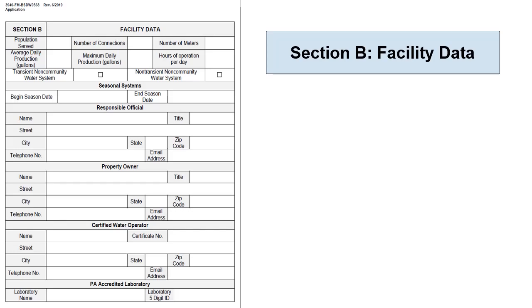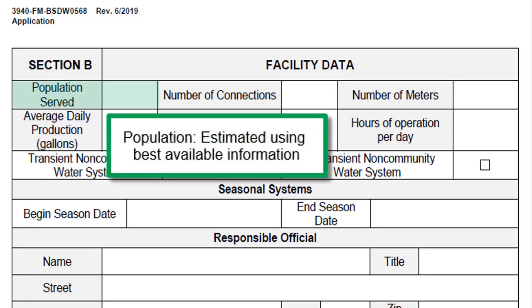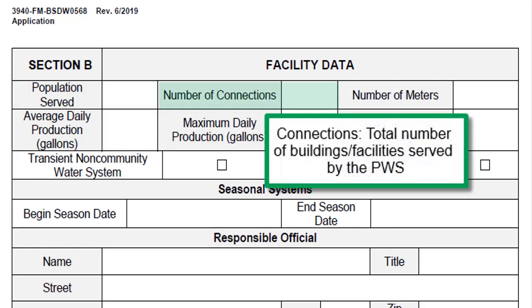Section B on the application is for facility data. The population served per day may have to be estimated using the best information available from the system. For a restaurant, this may include counting the number of receipts for the day, total number of employees, reviewing total water usage, and utilizing any other relevant information. For a hospital, this may include the number of patients, employees, and estimated number of visitors. The number of connections should equal the total number of buildings or facilities included in the water system.